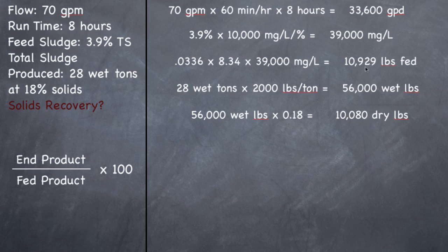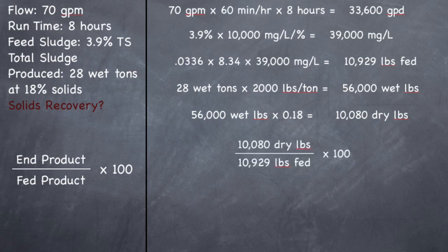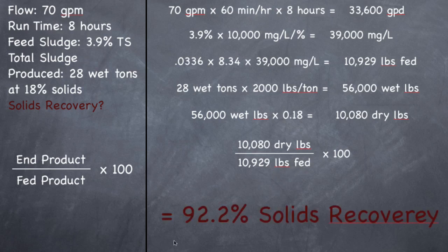You can see we lost almost 900 pounds of sludge in the filtrate — the difference between 10,929 and 10,080. So plugging into the formula: 10,080 dry pounds divided by 10,929 dry pounds fed, times 100, gives an efficiency of 92.2%. You're losing about 8% solids in the filtrate.